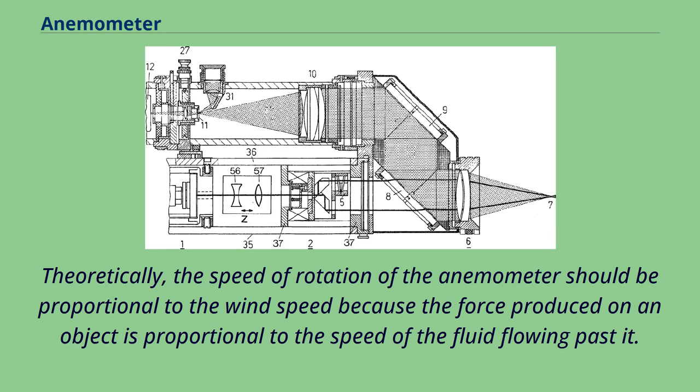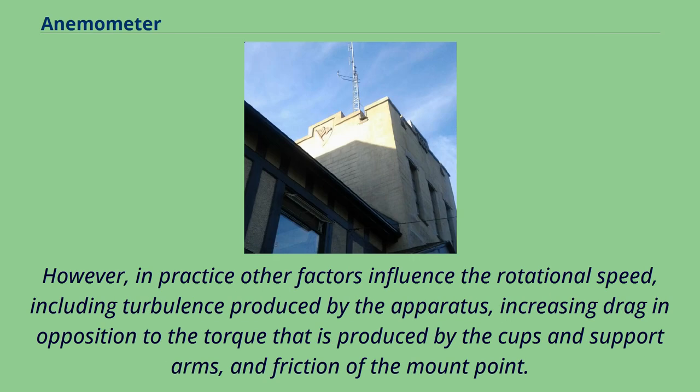Theoretically, the speed of rotation of the anemometer should be proportional to the wind speed because the force produced on an object is proportional to the speed of the fluid flowing past it. However, in practice other factors influence the rotational speed, including turbulence produced by the apparatus, increasing drag in opposition to the torque that is produced by the cups and support arms, and friction of the mount point.